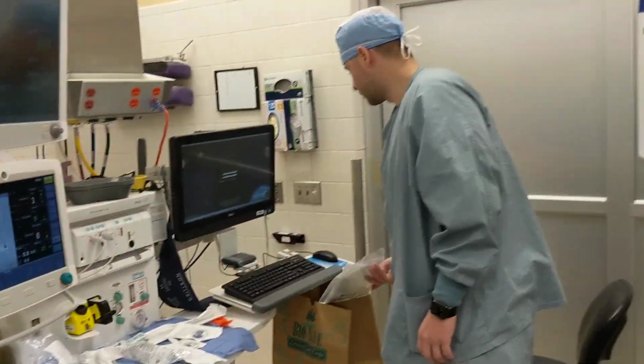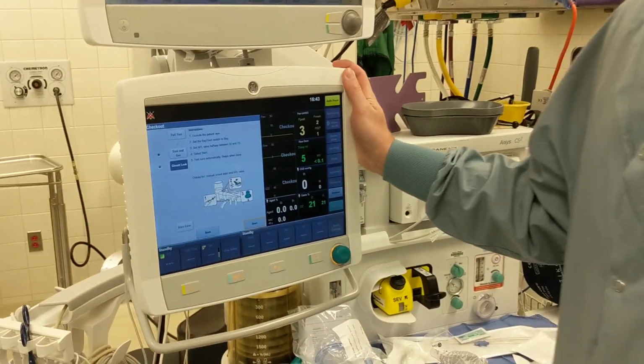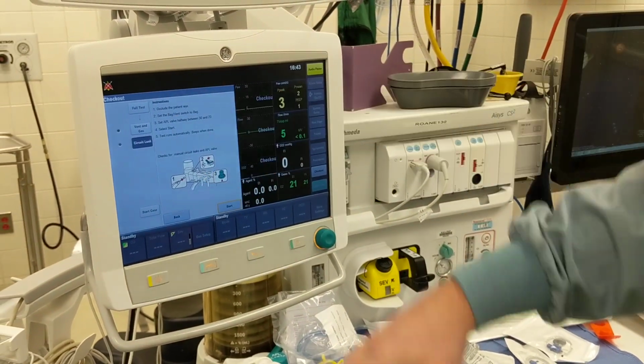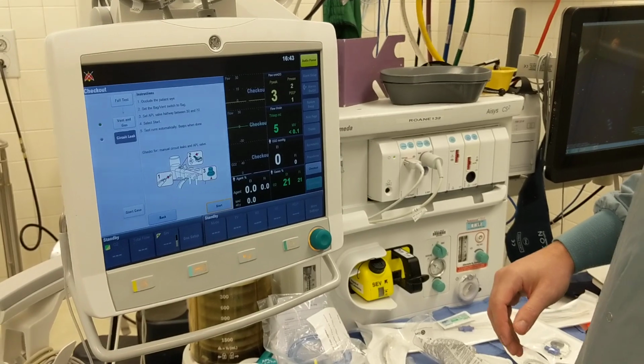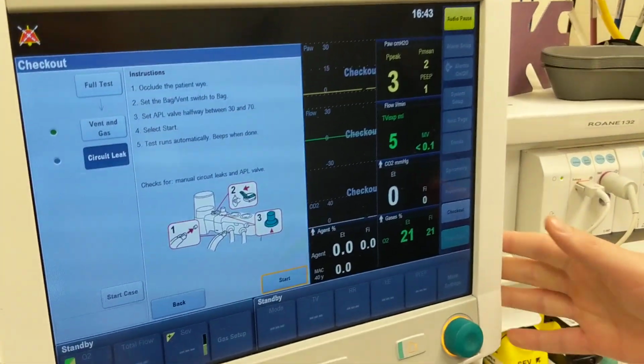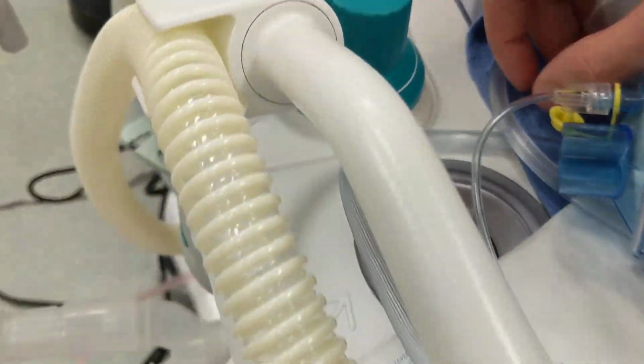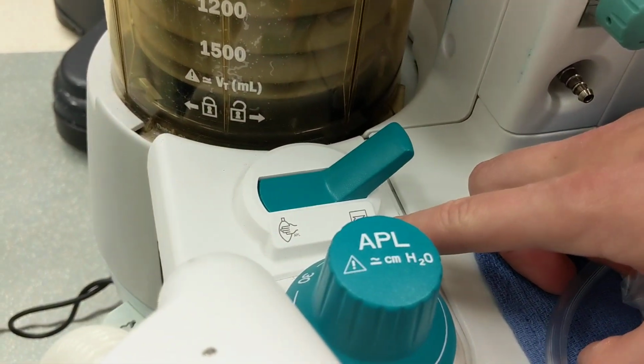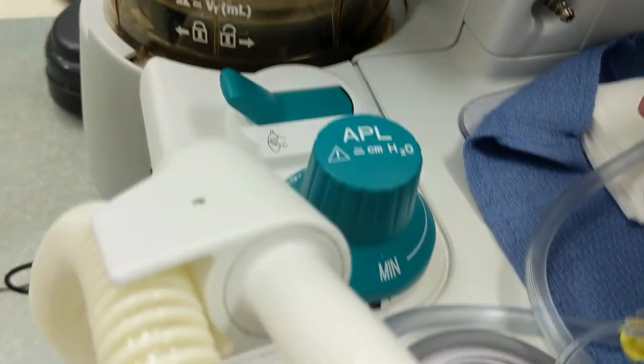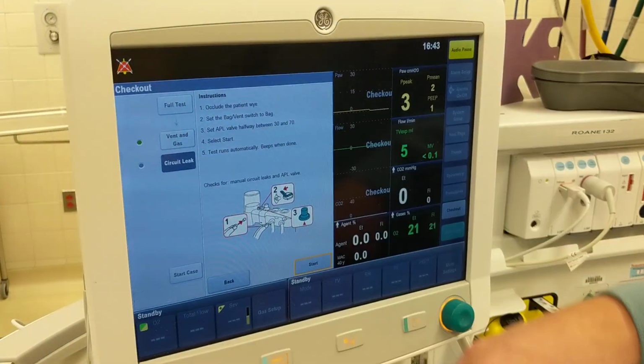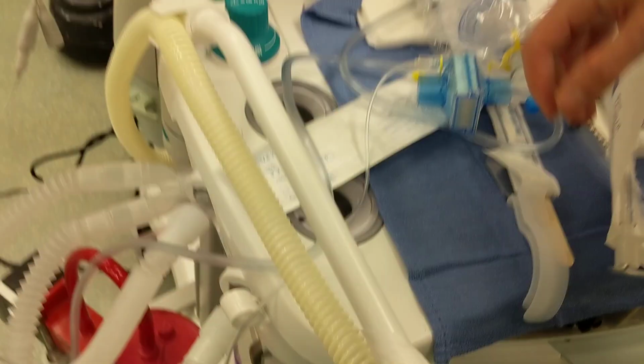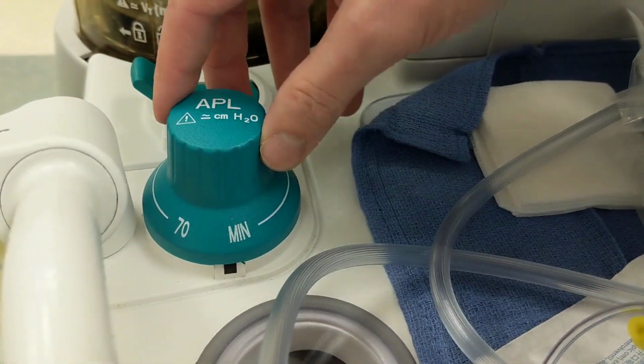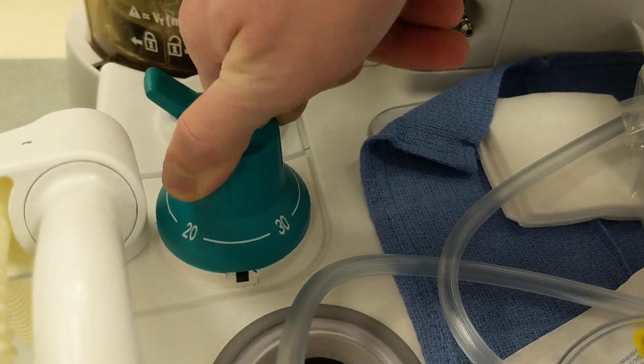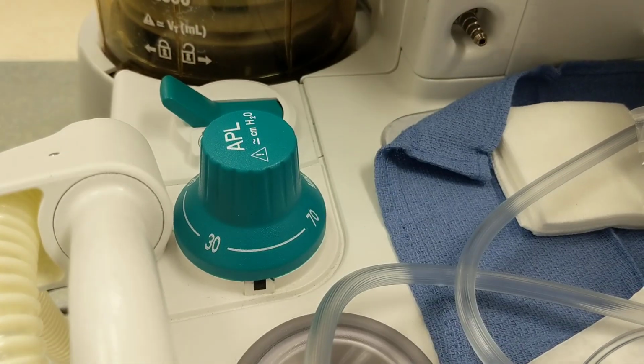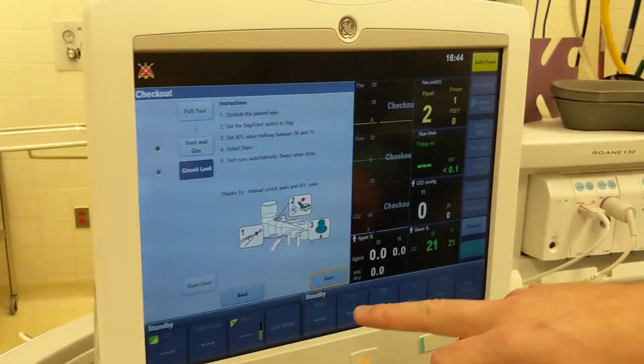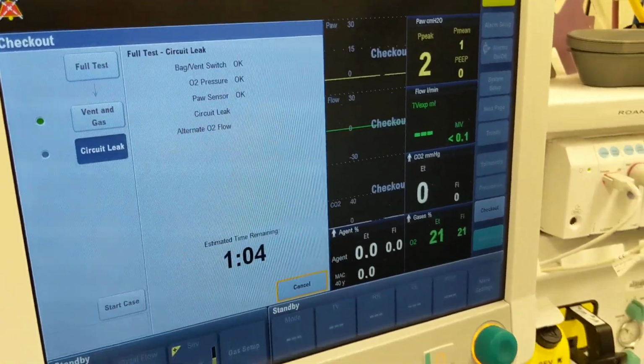And in the meantime, your machine checkoff is done with the next step. So once again, we're going to continue on with occluding the Y. We have that done from the first step. Set the bag vent, switch to bag. So we go back to the initial step. And here we are currently on the vent. We're going to switch over to the bag. Select the APL valve halfway between 30 and 70. This is your APL valve here for closing and opening. So in this case, we're going to go all the way to 30, 70 to close it. And we're going to hit start and let the test run.